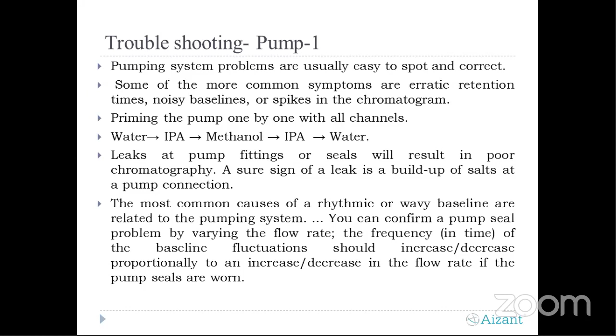Coming to the next point on the pump, I think the first point we have more or less discussed. If you keep your instrument properly, with preventive maintenance and taking care of all the parts, there will be fewer chances of challenges with the pump system. If your piston is broken, replace the piston. One of the major challenges is air trapped in the pump head. If you have an advanced system, it comes with a solvent degasser, which will degas all the air entrapped in the mobile phase, and you won't face challenges. But in the old systems, this degasser is not there, and there was a lot of challenge in the early eras that we had to face.